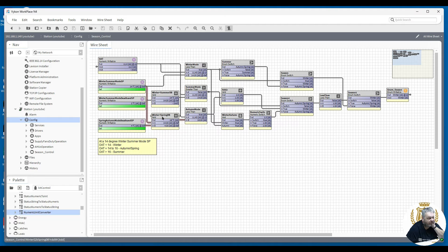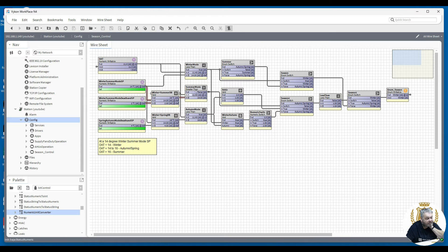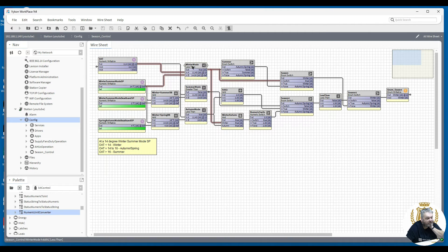You can see we've got winter, spring, summer outputs combined. So: if we're above 16 degrees, we're in summer mode; if we're less than 18 degrees, we're in autumn mode; and if we're less than 14 degrees, we're in winter mode. You follow that through — because we are in winter mode at the moment, that's true.